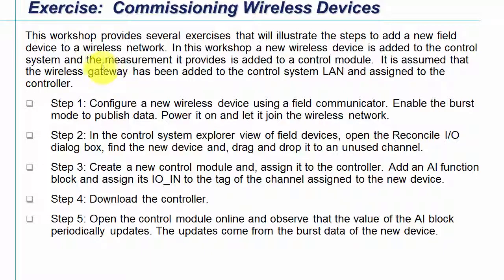It is assumed in the workshop that the wireless gateway has already been added to the control system. Initially, we will take a new wireless device, and using a field communicator we'll enable burst mode communications and power it up. We'll then go to the Control System Explorer view and show how the information from the wireless device is assigned to a channel within the control system.